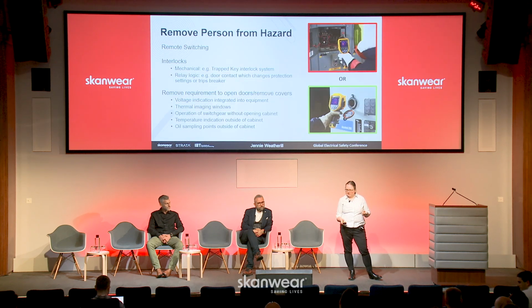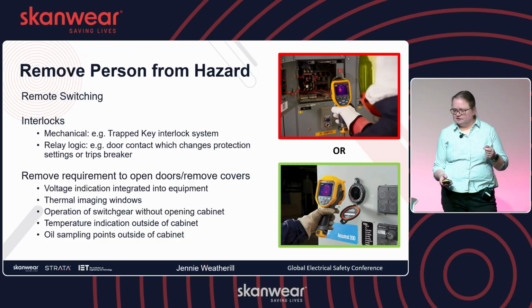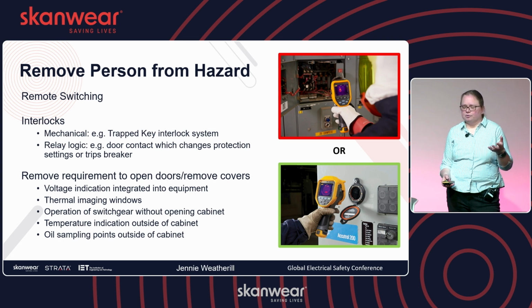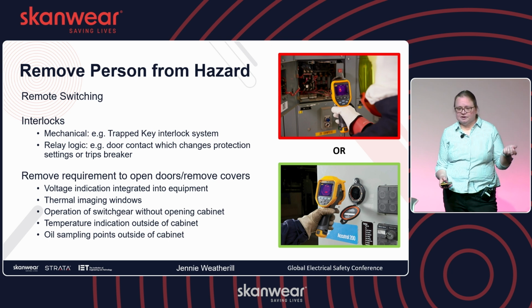So going back again to removing the person from the hazard, one of the tools is remote switching. We'll go into that a bit later. Interlocks, we've had discussions on those. Mechanical interlocks, trapped keys, again, there'll be examples later. Relay logic: for example, in a wind turbine, you've got intruder alarms on the door. Can you use that sensor to actually switch off the kit before anyone goes in there? Just some ideas to throw around.